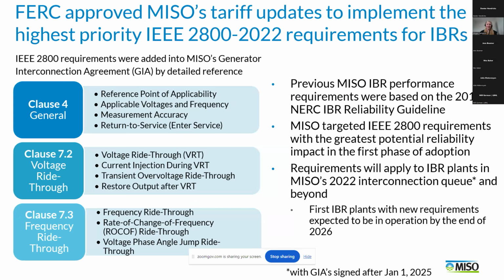So given all that background, here is the summary of where we landed for the first round of IEEE 2800 adoption. The requirements that we implemented were from 3 main sections of the standard. The first was clause 4, which is like the general clause. From there, we included the subclauses that detail reference point of applicability and applicable voltage and frequency, as both of those contain pretty essential definitions and details that the rest of the standard does rely on. We also included the subclause on measurement accuracy. And the thinking there was that if we do want to implement ride-through requirements, the IBR plant should have good measurement accuracy. Otherwise, those ride-through requirements and associated protection settings won't be effective if the plant is taking in bad voltage or frequency measurements. And then the last part of clause 4 we adopted was the section on return to service and enter service.